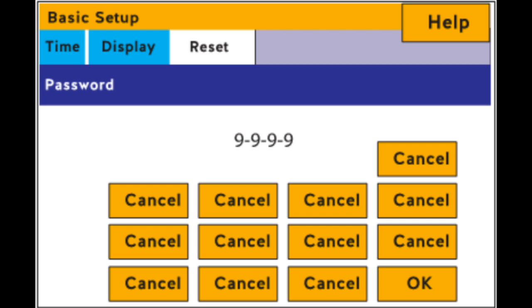Now the password for factory reset is 9999 and then select ok and the inverter will shut down and reboot and once it reboots you probably will have a beeping sound because the battery is not configured.